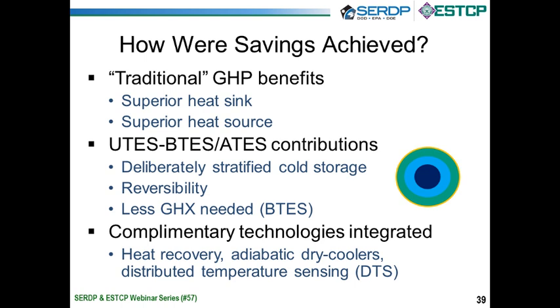The complementary technologies I want to talk about, if we have time, and it looks like I've still got a little bit of time, is heat recovery. We've hit on that a little bit already. This is the six-pipe water-to-water heat pump where we're connected to the ground, the BTES, but we're also connected to chilled water and hot water. And honestly, a lot of the time in the winter, we're just taking the heat out of the cooling, the chilled water coils on the air handler. It's going out to the building. Normally, it goes through a true reheat VAV box with gas being burned and hot water reheating that air back up. We're just taking free heat off of the compressors, feeding it to the VAV boxes at low heat, 105 degrees, say, and we're reheating the air for free, if you will. And so that was a really good technology, the heat recovery heat pumps.